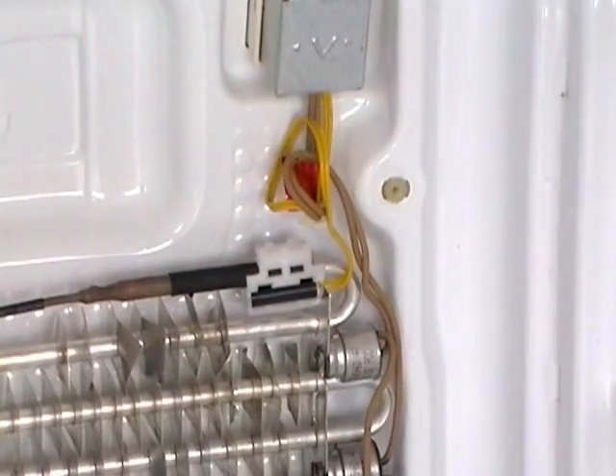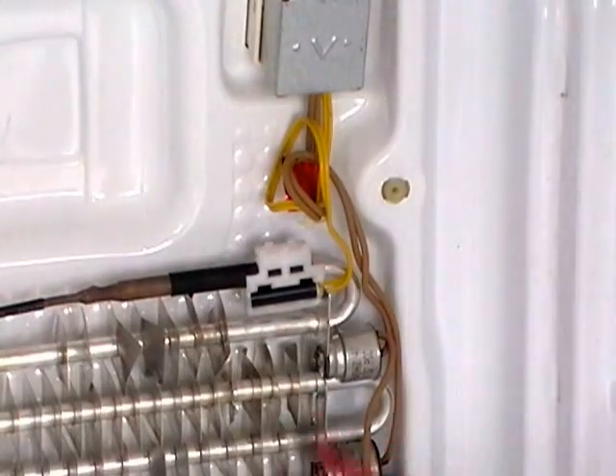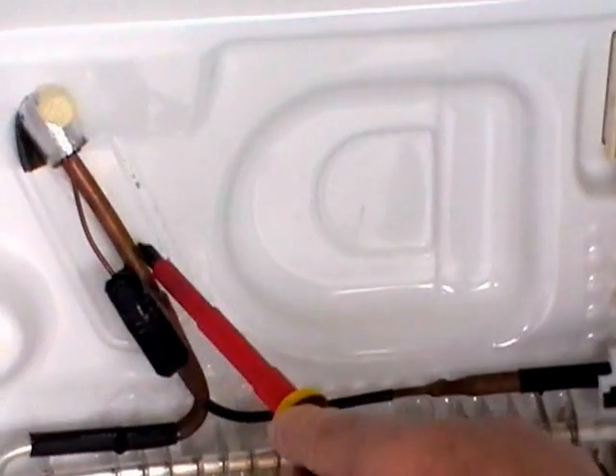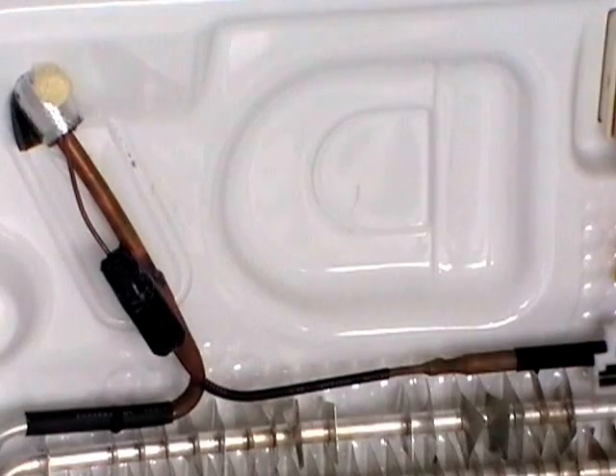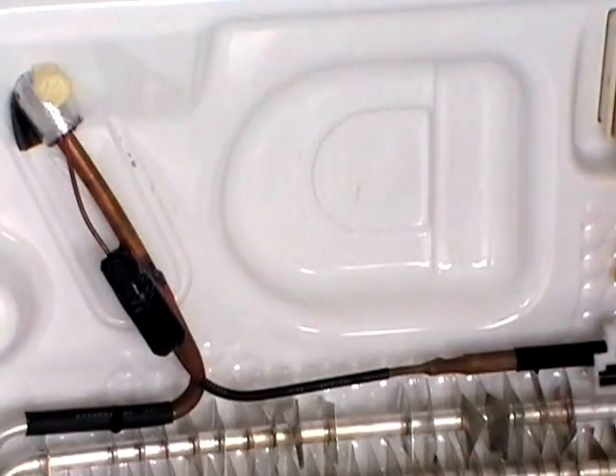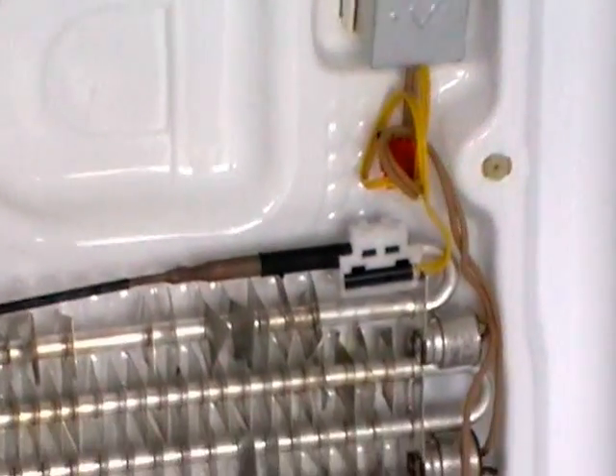Part of the modification is the black headed sensor that you can see there — it needs to be moved over to the refrigeration tube there. It requires a new sensor because the existing one's wires aren't long enough. This sensor on the RS-H1 is white and we're about to show you how to do it.